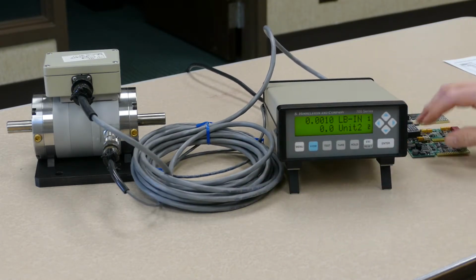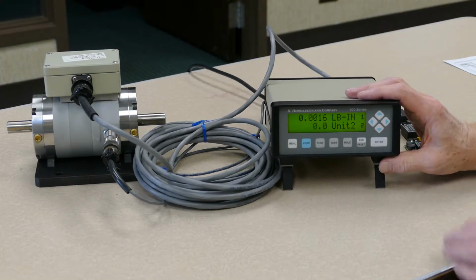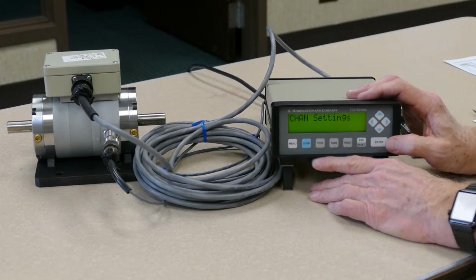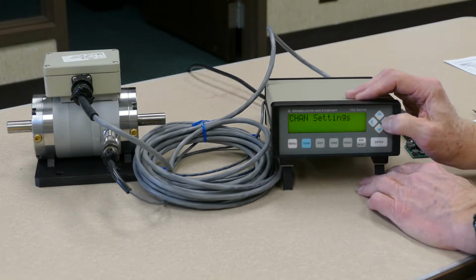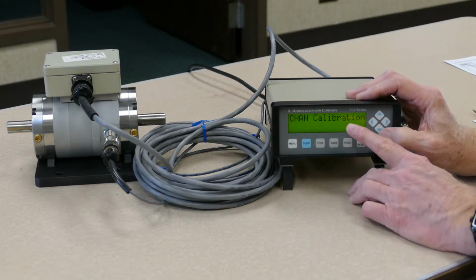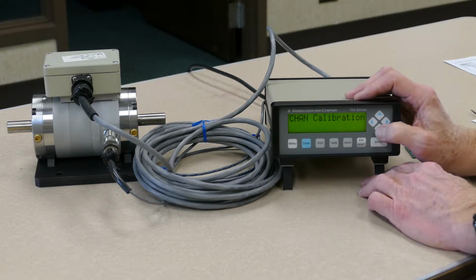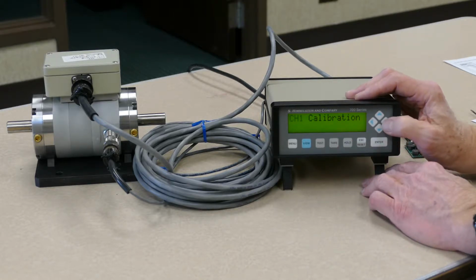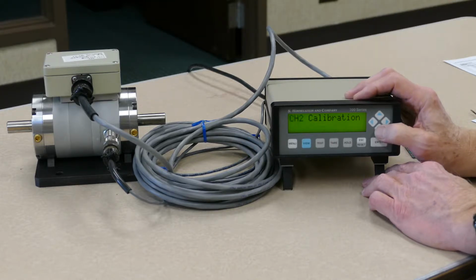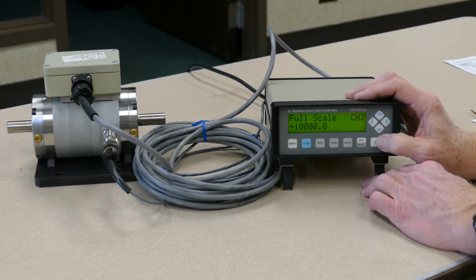To configure the input for the speed pickup, you press the menu key. Use the right arrow to scroll until it displays channel calibration. Press the down arrow. The speed pickup is in channel 2, so we want to hit the right arrow to scroll until it displays channel 2 calibration. When that is correct, hit the down arrow, and now it will ask you to enter the full scale value for the speed pickup or for the speed measurement.